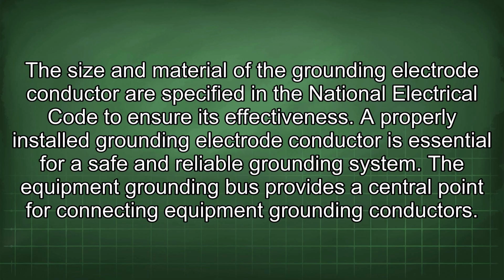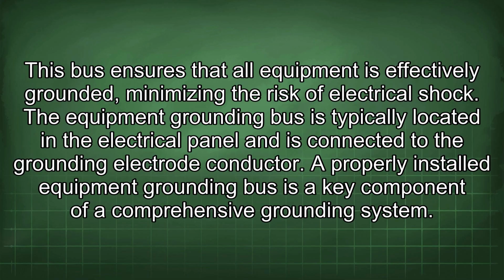The equipment grounding bus provides a central point for connecting equipment grounding conductors. This bus ensures that all equipment is effectively grounded, minimizing the risk of electrical shock. The equipment grounding bus is typically located in the electrical panel and is connected to the grounding electrode conductor. A properly installed equipment grounding bus is a key component of a comprehensive grounding system.